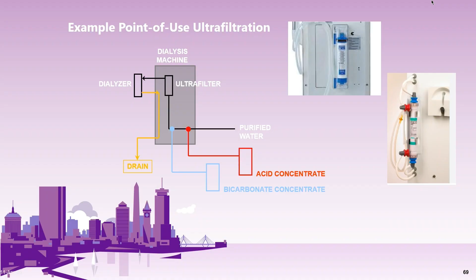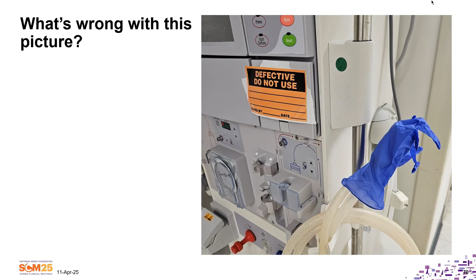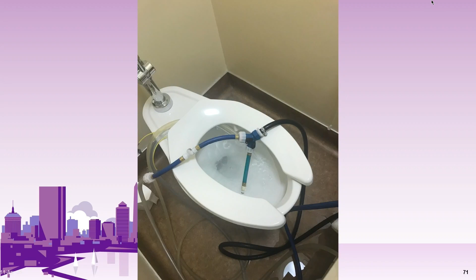It's located in different parts of the components. And what's wrong with this picture? That's both the water line feed and the drain line. So if caregivers, please tell them, separate the two. And then look at this. What does that say? What's wrong with the machine? We hate it when a clinician says it's broken. What are we supposed to do with that? So we have these so that there are lines that you can fill in to say what it is. And then obviously this picture is self-explanatory. That's actually a water line, a feed line to the machine. And then the last one is this.